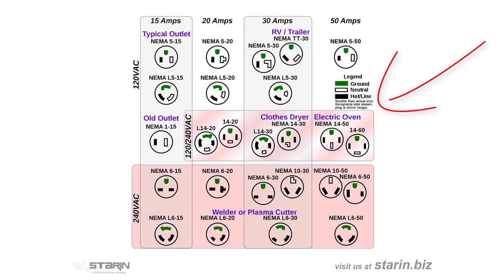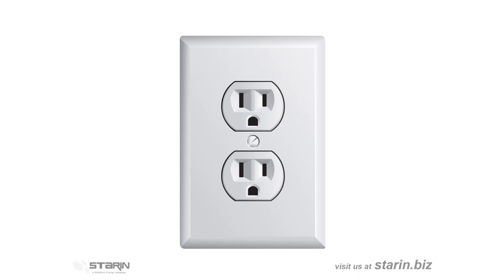Most of the products we work with use simple 15 amp circuits, which use this familiar connection. While a lot of old timers just call this an Edison plug, the real name is NEMA 5-15. It has two vertical prongs for live and neutral and the third peg for earth ground.